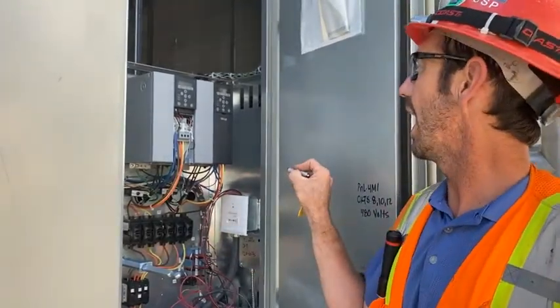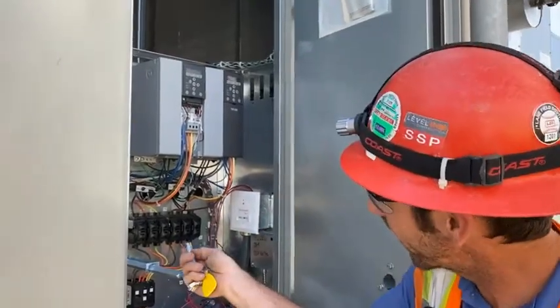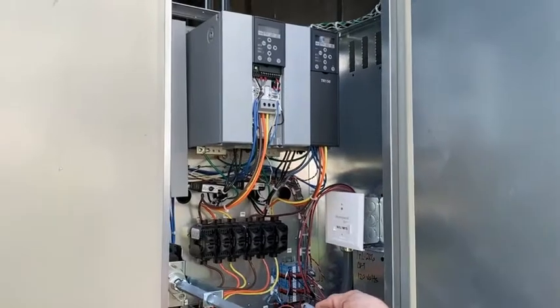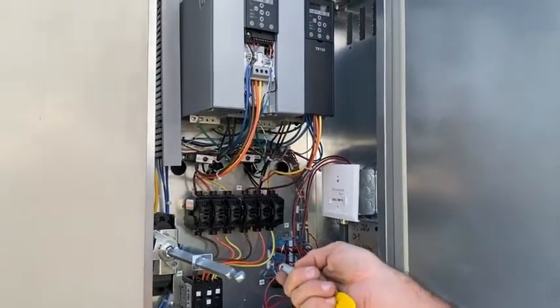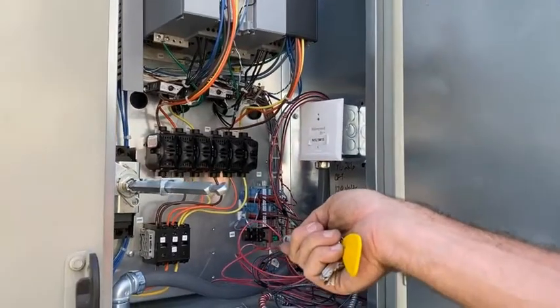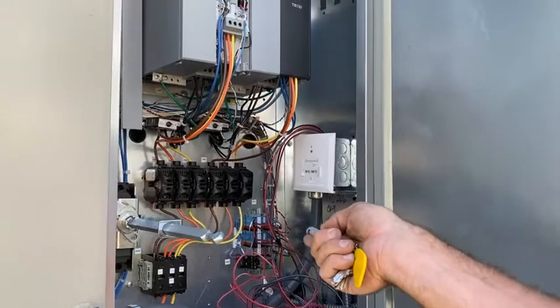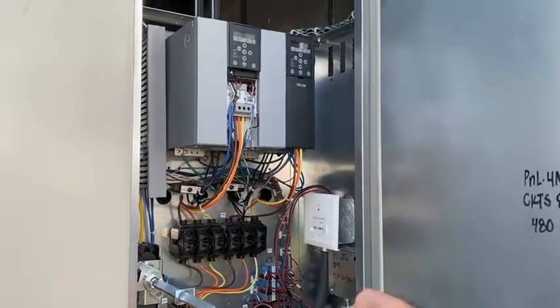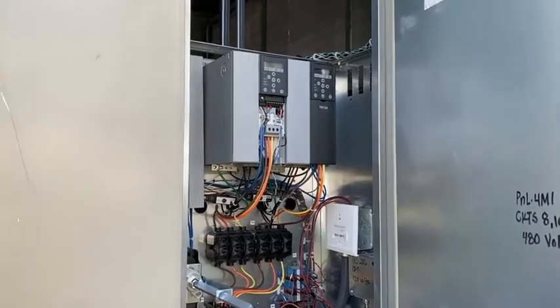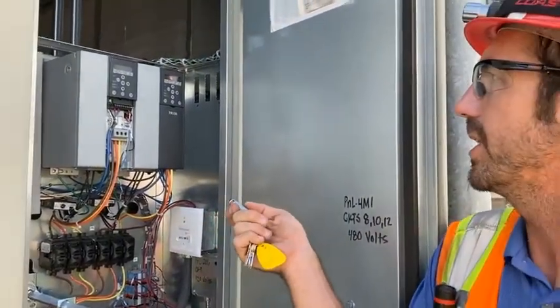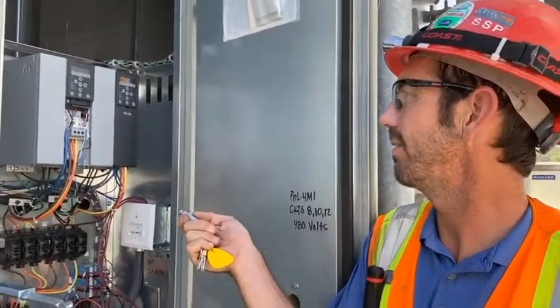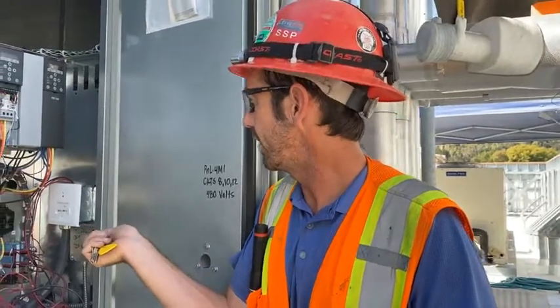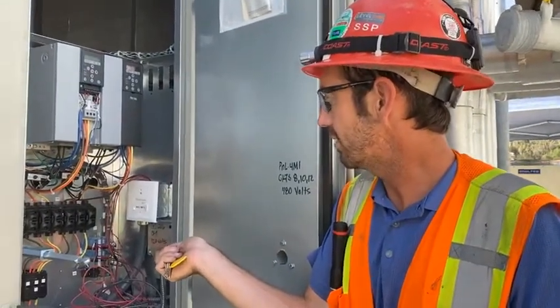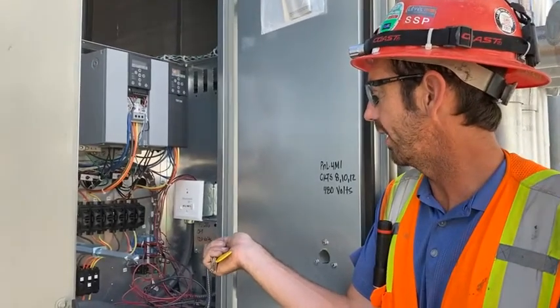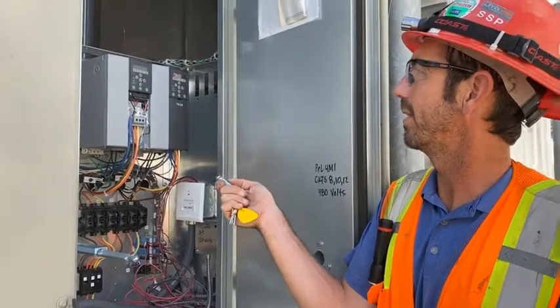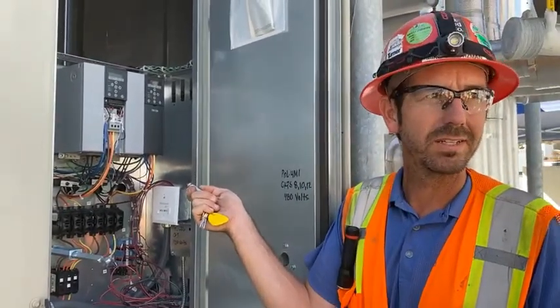You got output here to the motor. You got input down here into the drive from the fuse block right here. So it goes in the main disconnect here at the top, goes out through this load block, and then it splits there into each input fuse to each drive. None of the connections from the field were made up here, except for the communication wire, I believe. Everything else is made down on this terminal block. You can start checking any kind of troubleshooting you need to do down here. And if you have the voltage here, then you'd want to come up to this panel and verify it here. Or you can start here first. It's up to you guys.